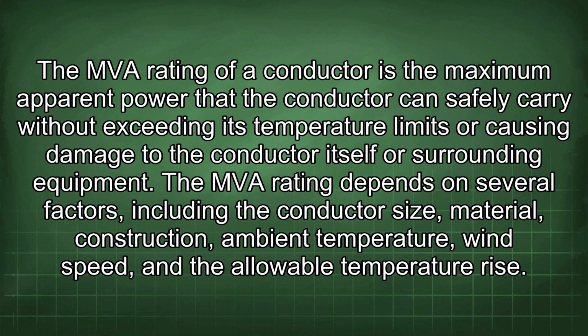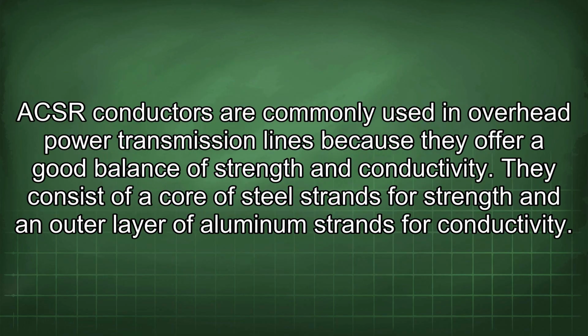The MVA rating of a conductor is the maximum apparent power that the conductor can safely carry without exceeding its temperature limits or causing damage to the conductor itself or surrounding equipment. The MVA rating depends on several factors, including the conductor size, material, construction, ambient temperature, wind speed, and the allowable temperature rise.